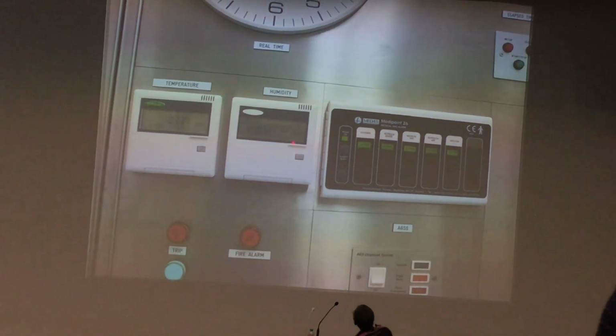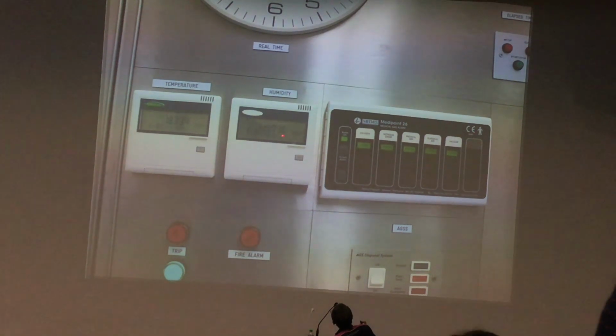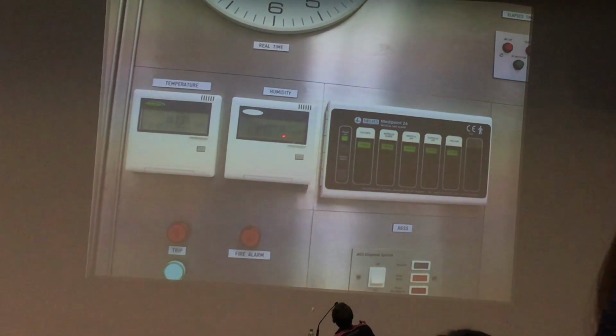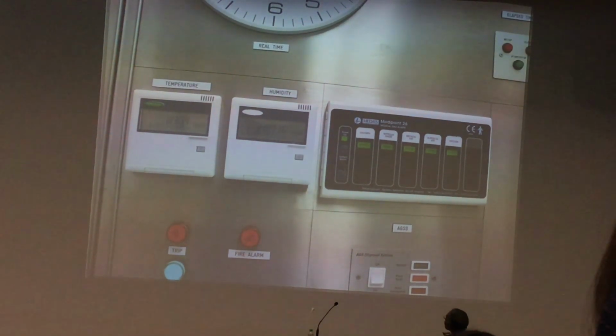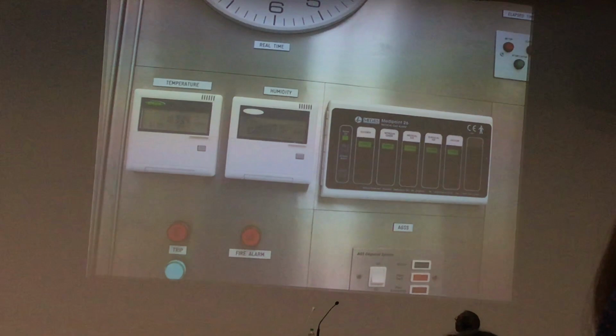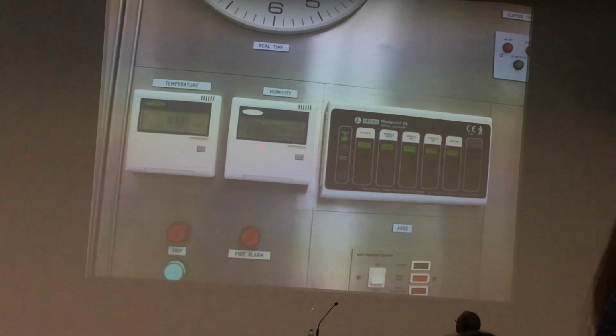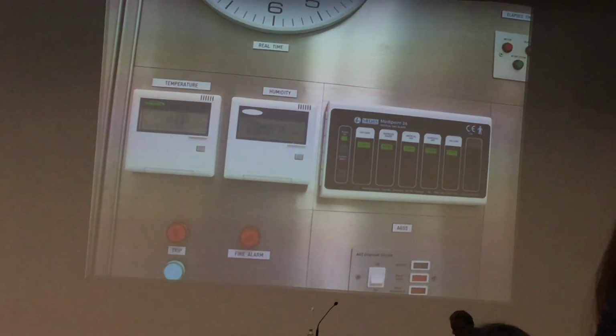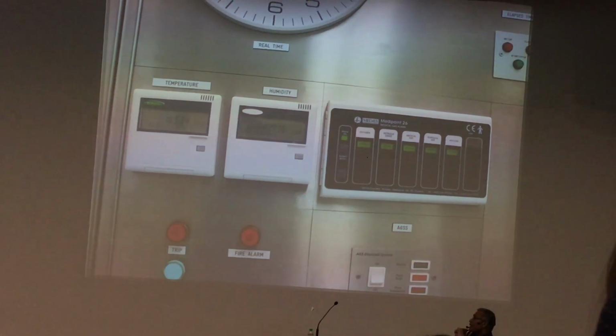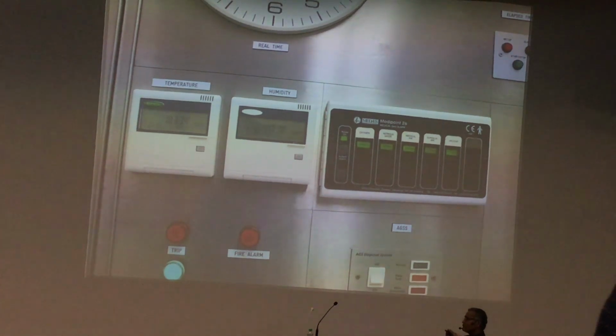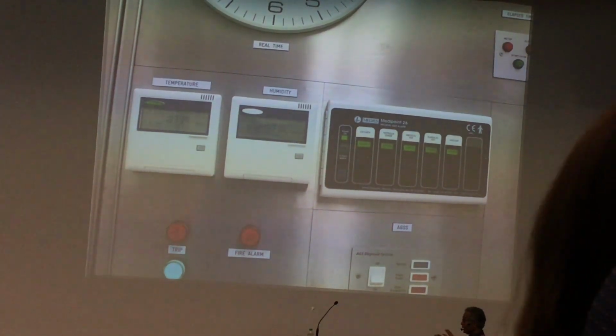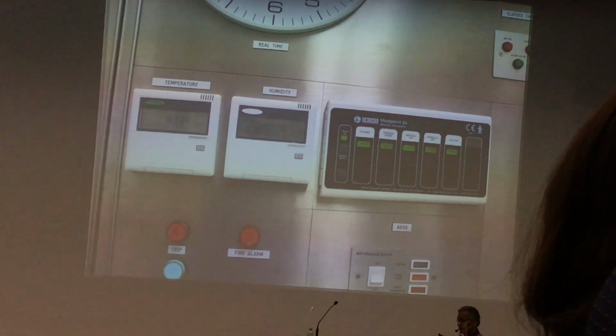What is this? 36, 39. 36. It's very low. So I think this is two sets of humidity and temperature measurement. So 18, 17. I think two sets just to compare. Humidity 39, 36. Okay. Ideally, for the main OT, ordinary OT, temperature 18 to 20, adult OT. Humidity 50 to 55. This is very dry, 36.